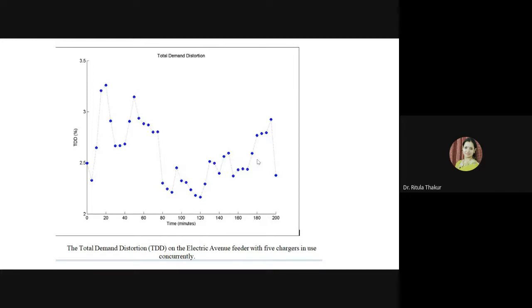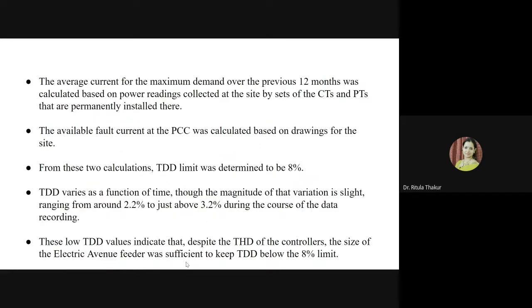But in order to have a broader overview, when we implement so many EVs in an EV charging station, it may happen that many different vehicles are getting charged at the same time. So this figure gives you that idea when all the 5 chargers were in use concurrently, and we can infer from this the average current for the maximum demand over the previous 12 months. They collected the power readings from the site by a set of CTs and PTs, from the figure which I just showed you. From that data, the average current of the maximum demand, because it's a total demand distortion, was calculated, and available fault current was also calculated.